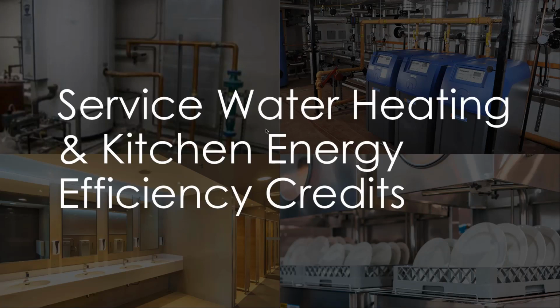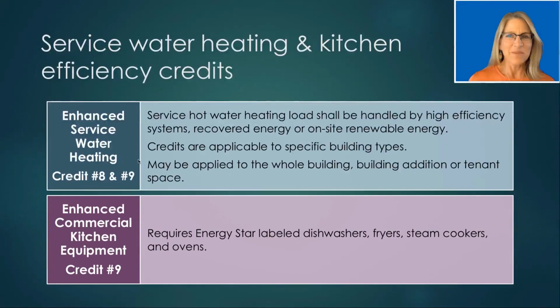So now let's talk about service water heating and kitchen energy efficiency credits. There are 2 service water efficiency credit packages and a credit for enhanced commercial kitchen equipment. To comply with the service water heating efficiency credit, the service water heating load shall be handled by high efficiency systems, recovered energy, or on-site renewable energy. The credits are applicable to specific building types, and may be applied to the whole building, building addition, or the tenant space. The enhanced commercial kitchen credit requires Energy Star labeled dishwashers, fryers, steam cookers, and ovens.